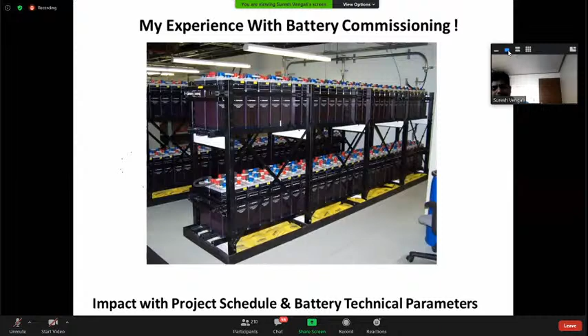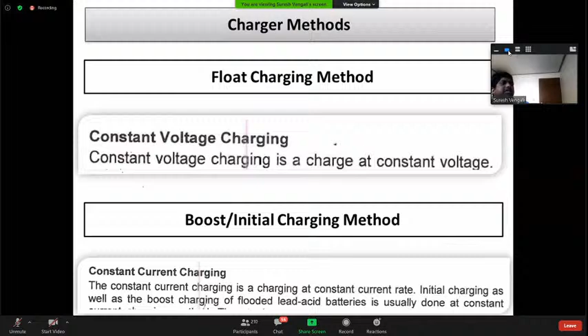So this is the battery room where temporary HVAC is providing ventilation. If I lost HVAC, if I lost power, if I lost my ventilation, what will happen? If you lose ventilation, and you charge the battery during that time, it is a high gassing point. If you are already charging the battery at a higher voltage like 2.75 volts, there is a high chance of gas leakage. So that is the reason you cannot charge a battery if you lose HVAC. You can only charge the battery when you have sufficient HVAC in the room. So that is very important.